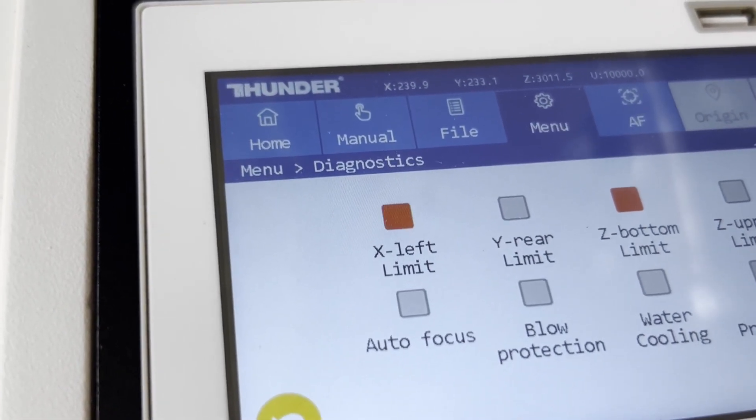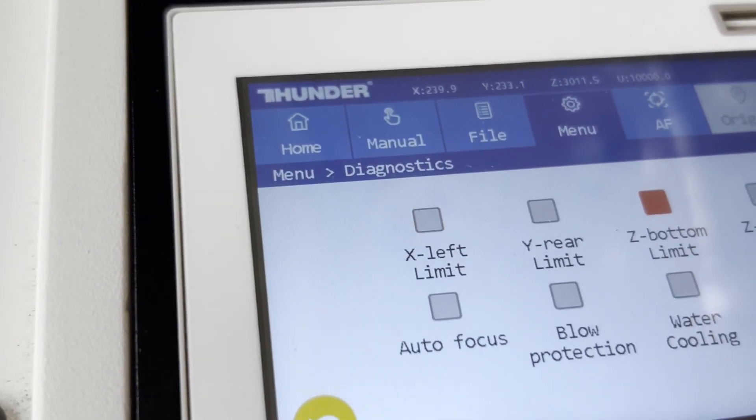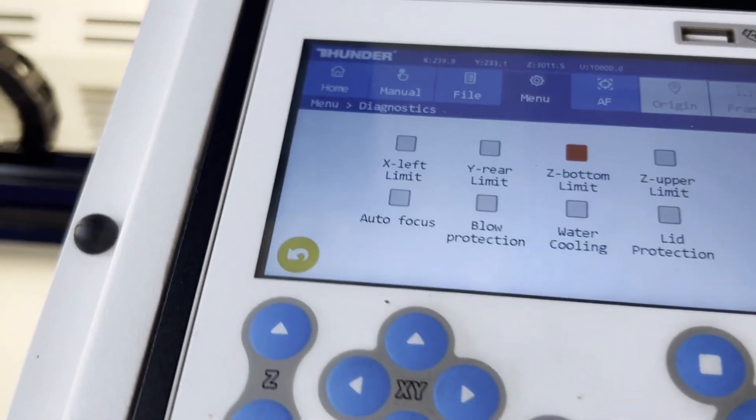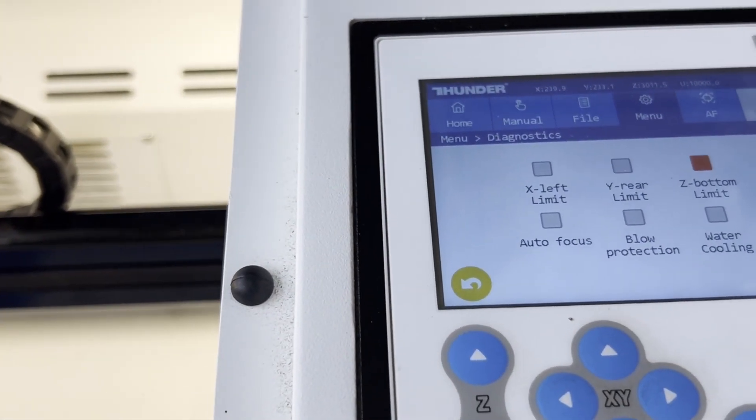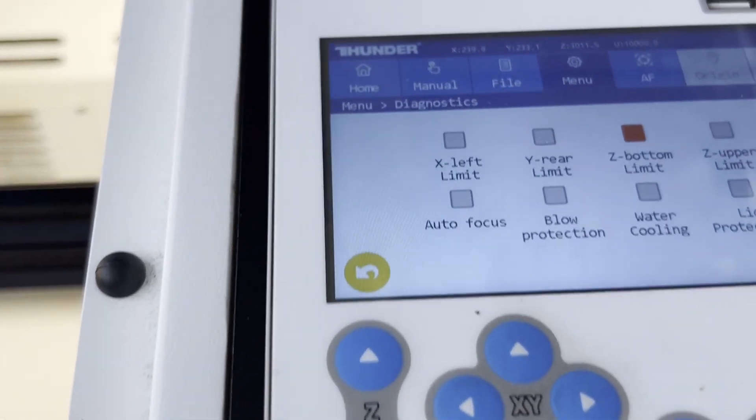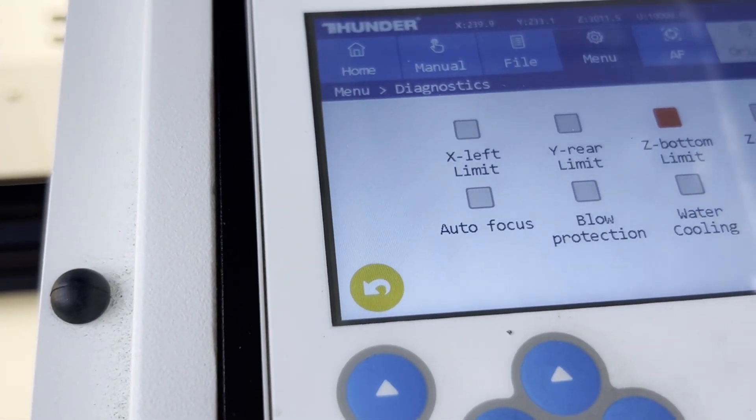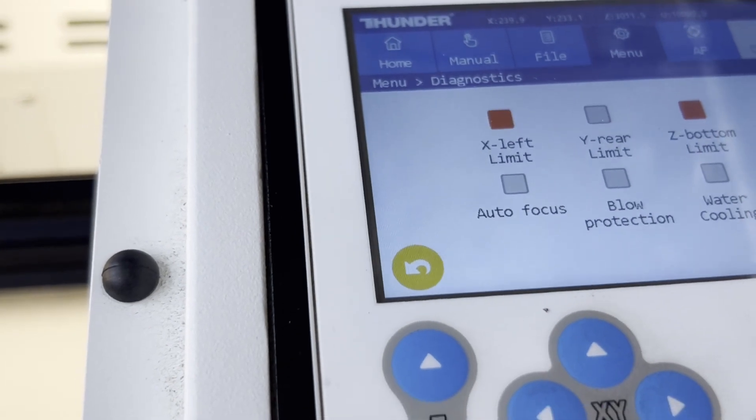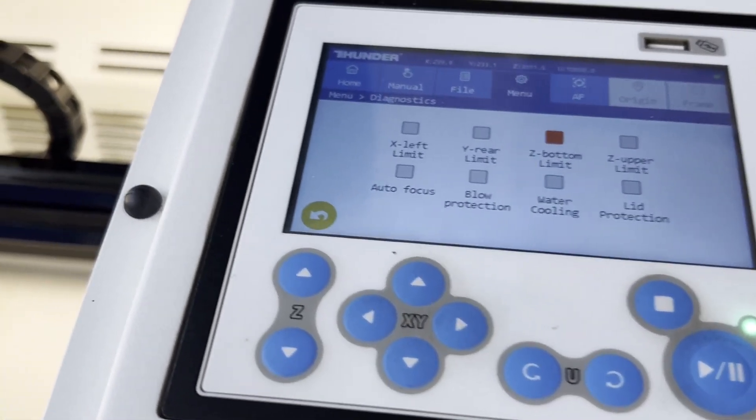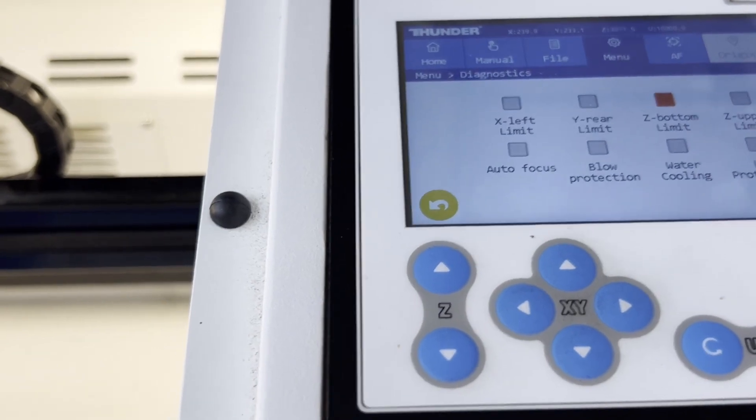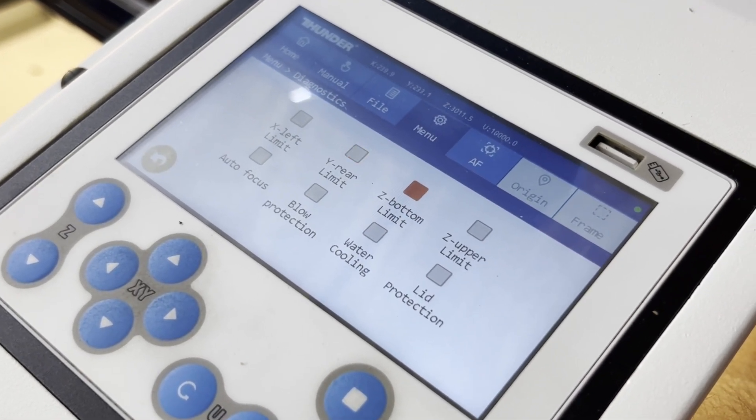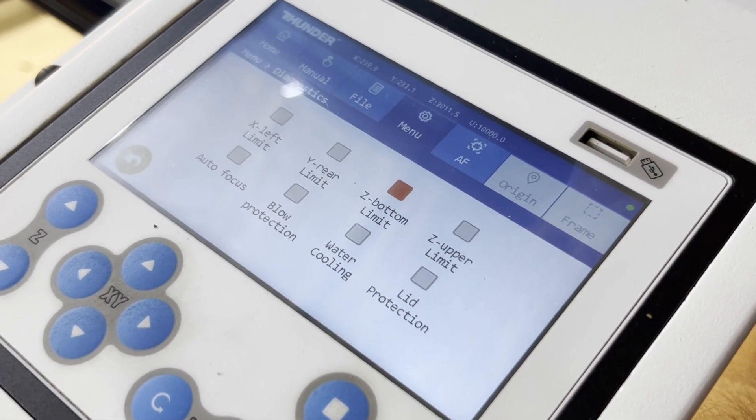And as long as this is working, then we know if it fails when you start it up or fails at any point in time, but we don't get a light when we press on the button, that means our arm that triggers the switch is not making contact and it just needs to be adjusted. If I go over here and I press this one, we can see that is working fine as well.